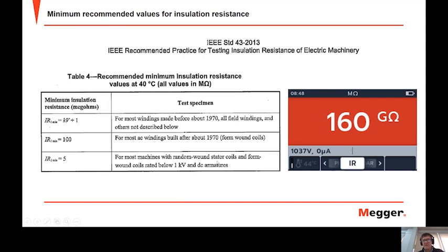And then for random wound windings below 1 kV, so this would be typically your low voltage motors, then we're looking for 5 megohms or greater at 40 degrees C. So these are the standards. These are the values that the standards recommend as a safe working minimum. But really 5 megohms is quite low if we're talking about reliability of motors. So we would recommend at least 50 megohms at 40 degrees when we're talking about reliability, or even higher, even the 100 that's suggested for form wound coils.